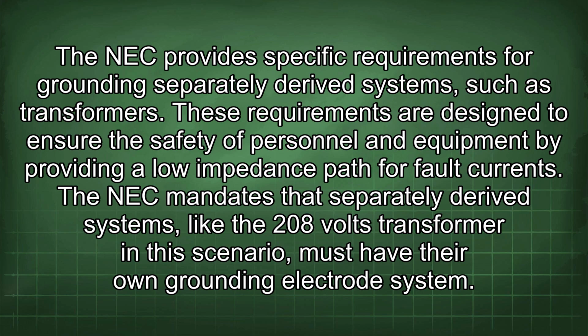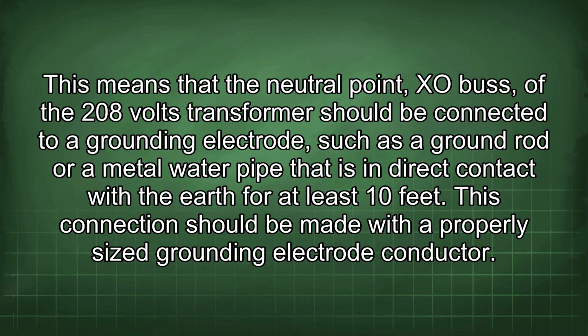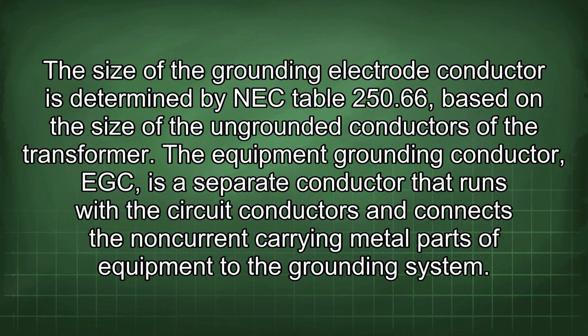The NEC mandates that separately derived systems, like the 208 volts transformer in this scenario, must have their own grounding electrode system. This means that the neutral point, XO bus, of the 208 volts transformer should be connected to a grounding electrode, such as a ground rod or a metal water pipe that is in direct contact with the earth for at least 10 feet. This connection should be made with a properly sized grounding electrode conductor. The size of the grounding electrode conductor is determined by NEC Table 250.66, based on the size of the ungrounded conductors of the transformer.